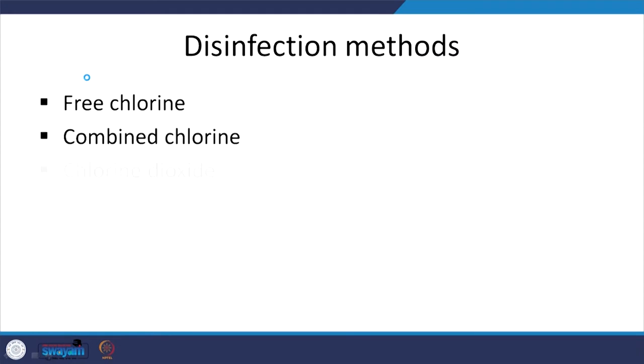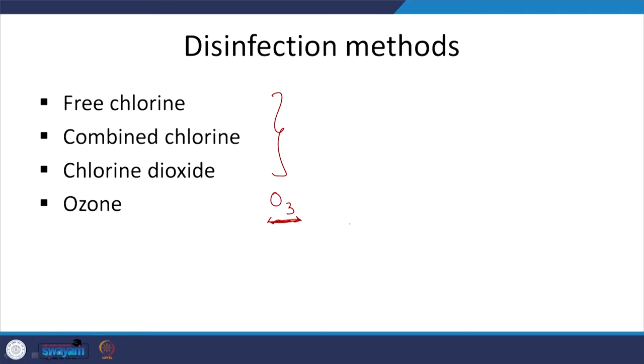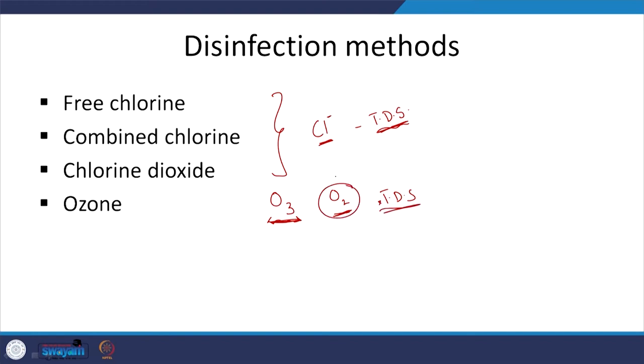Typical disinfection methods use oxidizing agents based on chlorine, and then ozone (O3). A reason for preferring ozone is that it increases the dissolved oxygen in your water and does not add dissolved solids — it does not add Cl⁻ which increases TDS. With O3, the final product is oxygen, which does not cause TDS issues. We also have UV radiation at 253.7 nanometers.